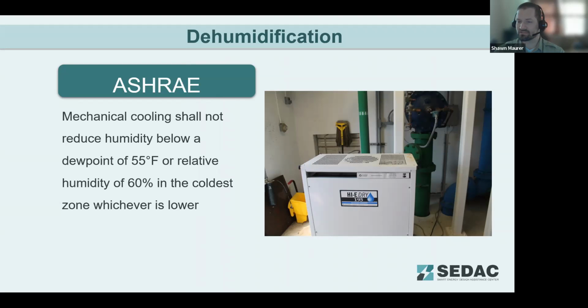There are exceptions for specific zones requiring specific humidity levels, such as museums and hospitals, where you want a little bit more humidity in the space. And those zones do have to be approved by the authority having jurisdiction or an accreditation standard. A 10% dead band, so a set point with a plus or minus 5 degree set point for the humidification and dehumidification is part of that requirement.